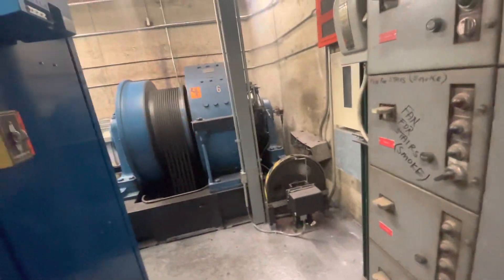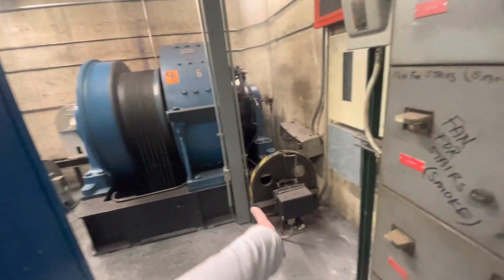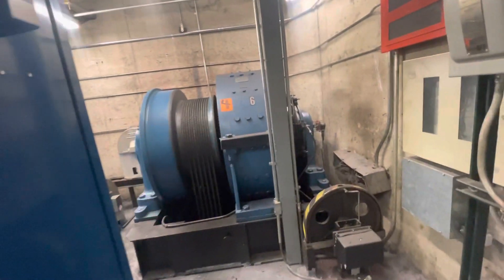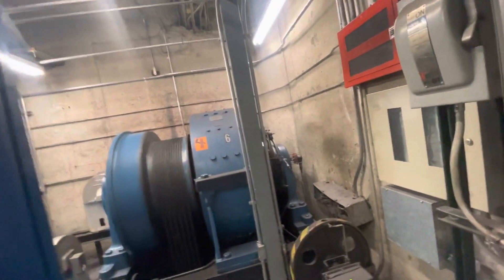This is definitely a DC motor, so you have to be careful stepping over this. Something's touching the encoder — right where the tachometer encoder is, something's scraping on that. You can see the commutator and the armature — there's the armature, and back in there is the commutator, and then there's the encoder on the motor.